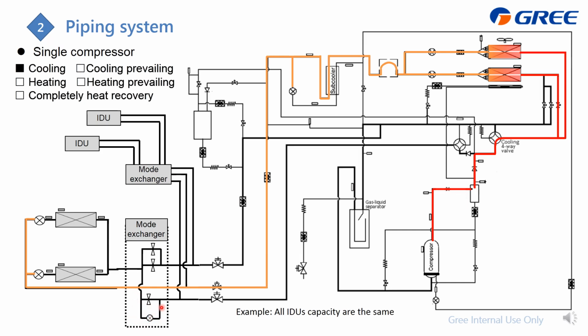And for the detail you can also go to the GMV6 heat recovery video. I have a little introduction for the mode exchanger, and it also maintains the liquid when we go to the indoor EXV, because there's no solenoid valve control at the liquid pipe. And this liquid refrigerant will get expanded here and become low pressure and temperature and absorb heat at the indoor heat exchanger, which is doing cooling.